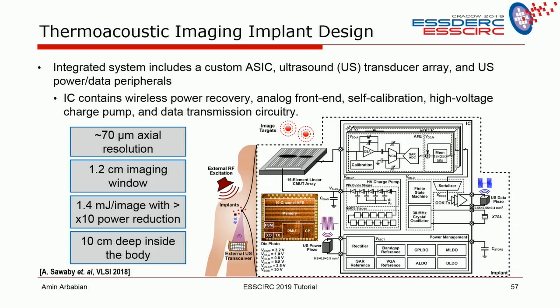It has about 70 micron of axial resolution, translating to about 30 megahertz of bandwidth. We do a 1.2 centimeter imaging window, so the whole window is about 1.2 centimeters. Inside of that, you have about 100 micron resolution. So this is not, obviously, it's inside the body. It's not for 20, 15 centimeter resolution. So the implant only sees the couple of centimeters around it.